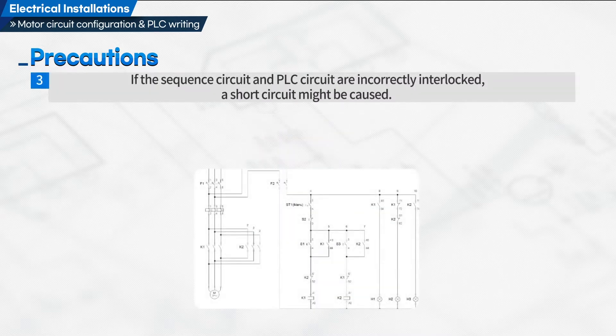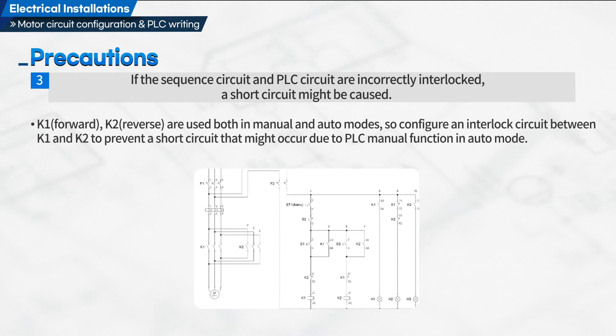Third, if the sequence circuit and PLC circuit are incorrectly interlocked, a short circuit might be caused. K1 forward and K2 reverse are used both in manual and auto modes, so configure an interlock circuit between K1 and K2 to prevent a short circuit that might occur due to PLC manual function in auto mode.